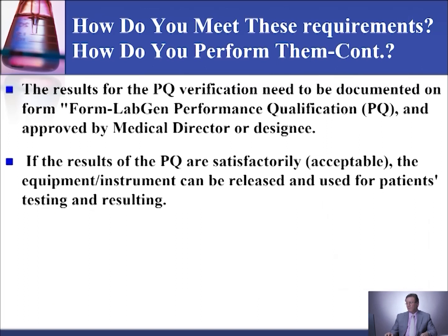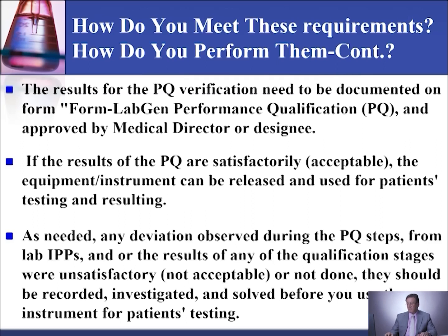The results for the PQ verification need to be documented on a form like the performance qualification form, and need to be approved by the medical director or designee. If the results of the PQ are satisfactory and acceptable, then the equipment or instrument can be released and used for patient testing and resulting. As needed, any deviation observed during the PQ stage from the lab SOPs, or any result of the qualification stages that was unsatisfactory, not acceptable, or not done, should be recorded, investigated, and resolved before you can use this instrument for patient testing.